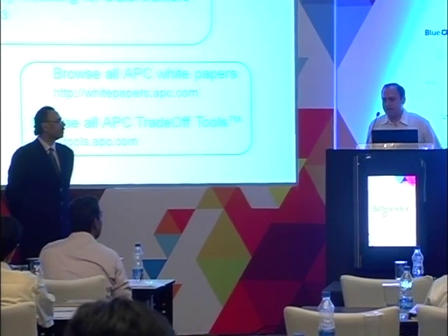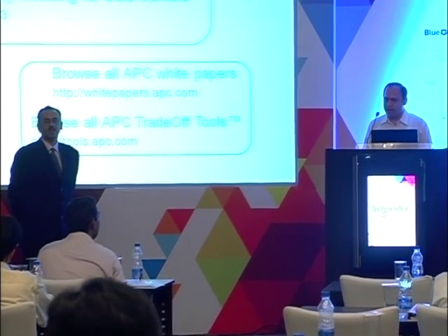Yeah, that's true. So there are actually three ways of looking at how to right size from a planning perspective, and these three ways are different because the scenario can be different for a particular data center owner. For example, if you already have a lot of data centers and you are looking at consolidating them, then getting data of actual consumption of servers is going to be easier for you. So in that case, I will recommend sizing based on actual consumption, because you have been using your data center for the last 5-6 years.